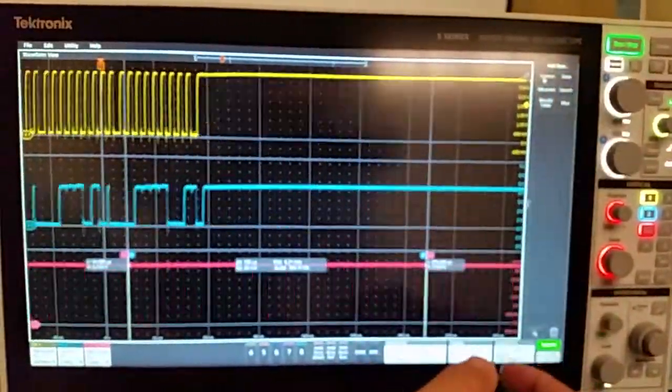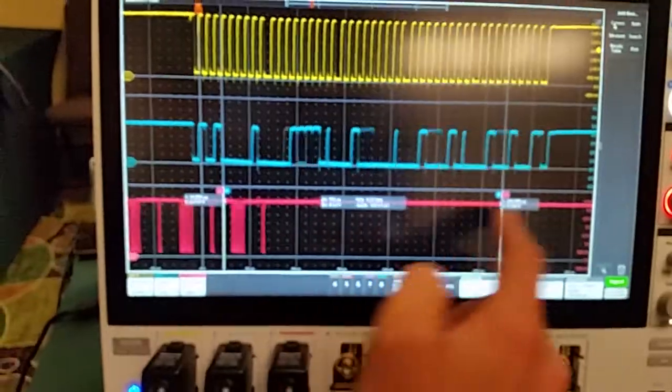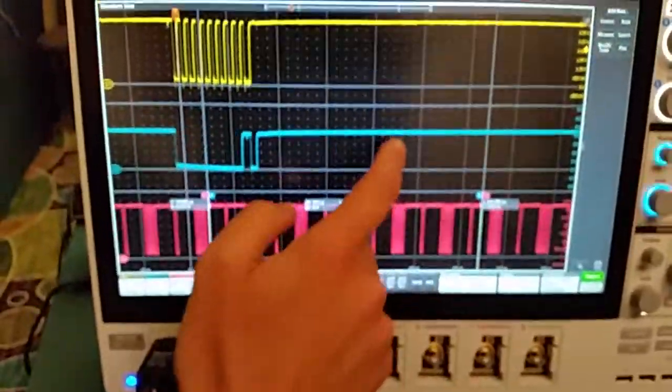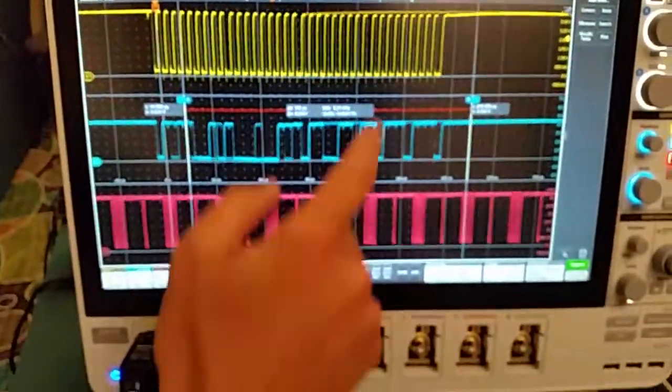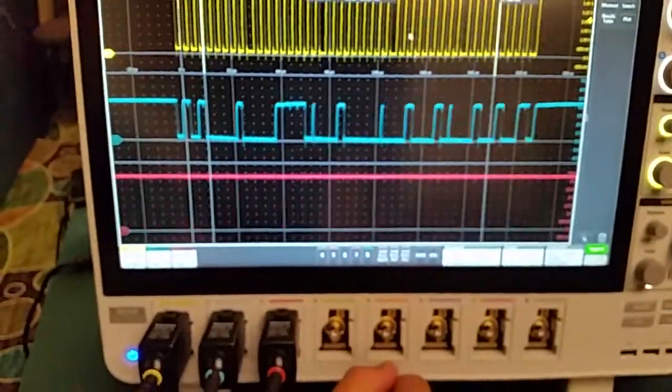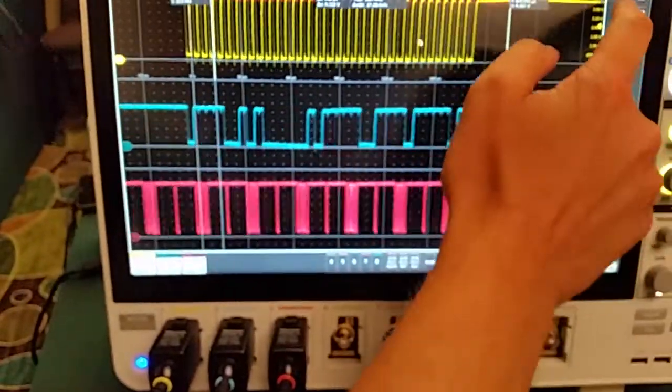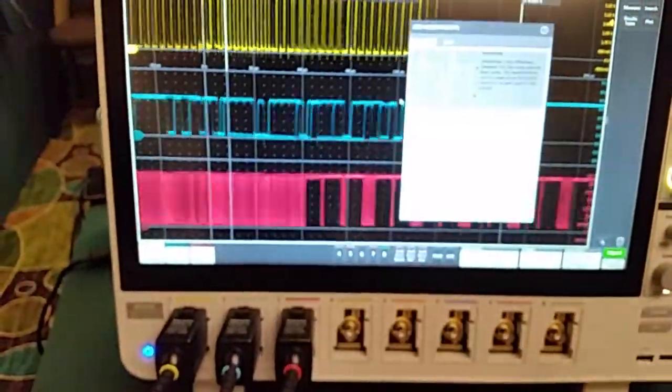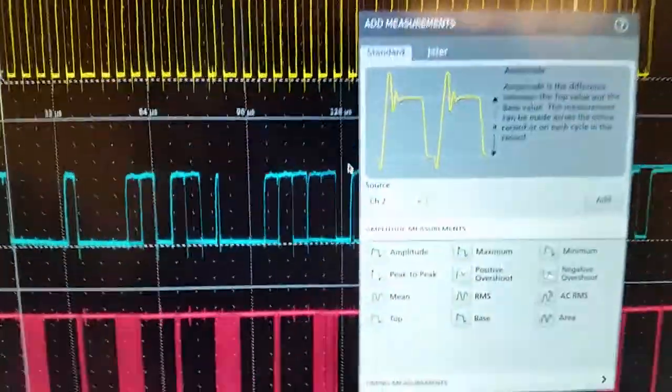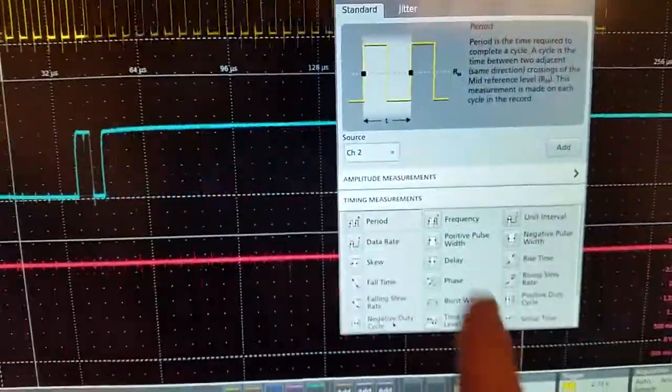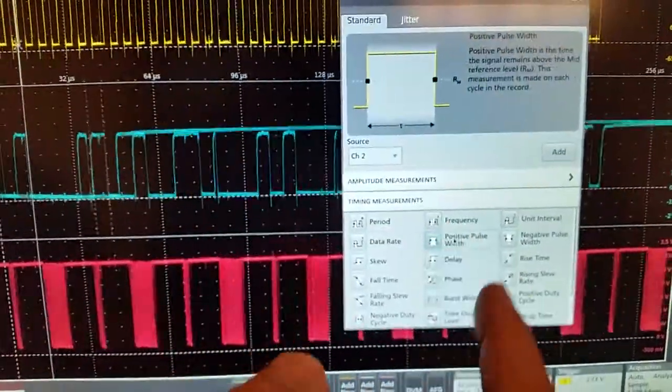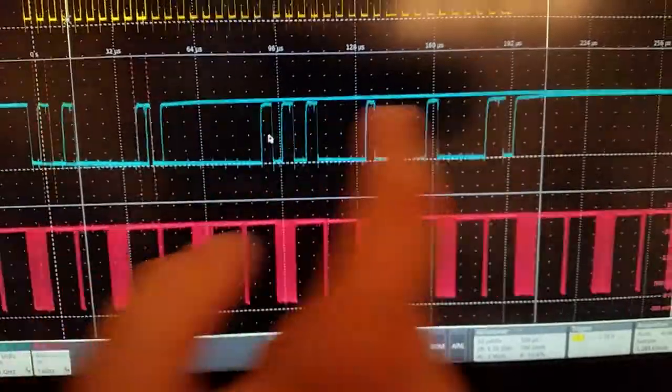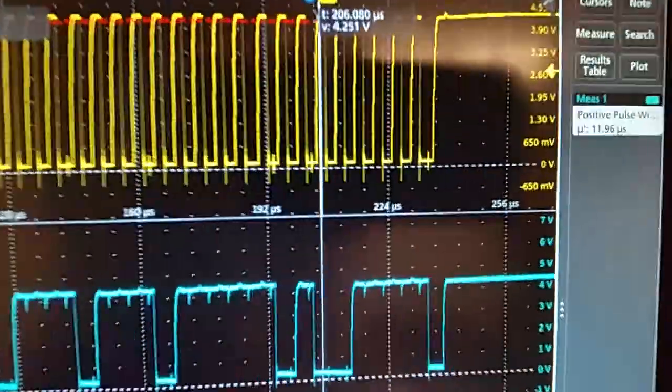So for example, I can turn on cursors. You see they appear in the display. If I want them on a different channel, just touch the other channel. If I want to turn on measurements, just drag measurements out. And maybe I'll turn on a positive pulse width measurement, which you see appears over here in what I call our results bar.